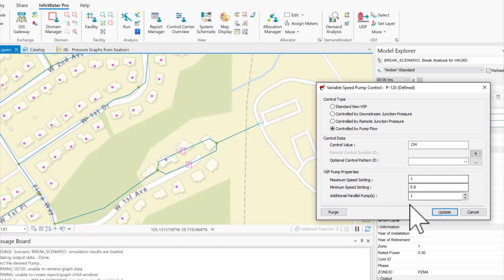So here's where you really need to check with your operating conditions, check with your operators to make sure you've got the right balance of how fast can this actually go, how big can this value be that I can plug into the pump affinity laws, and how low can this be here, right? So what is that range? And generally we don't advise for this to be over 1 at all, because that would be the pump actually going beyond its design curve.